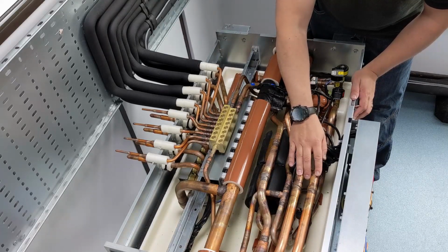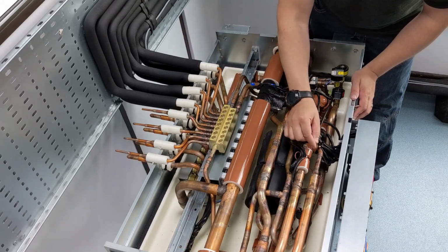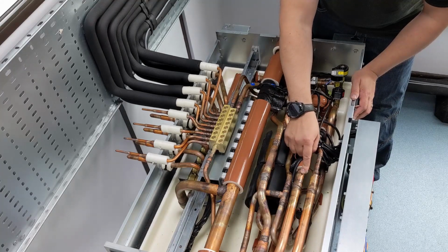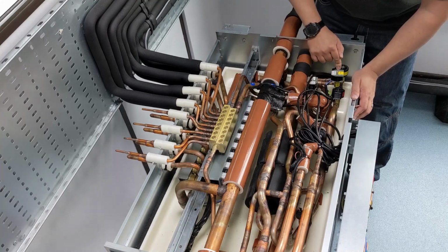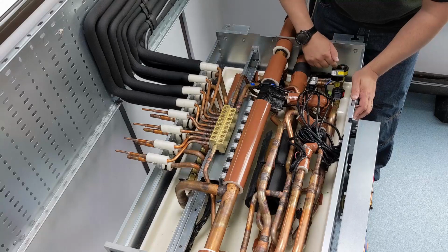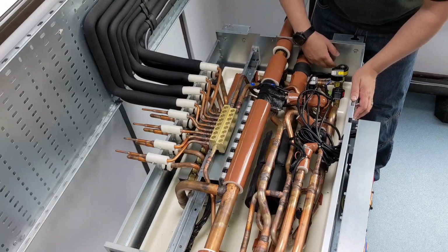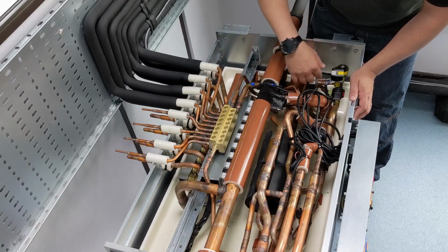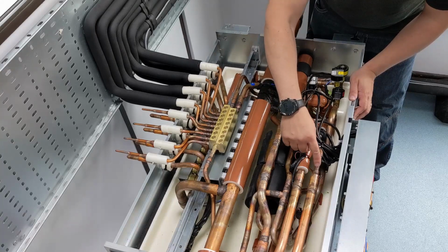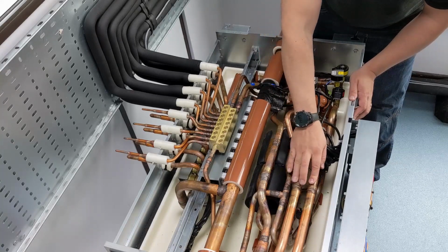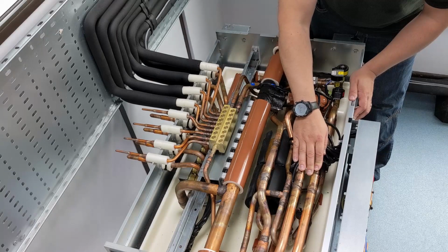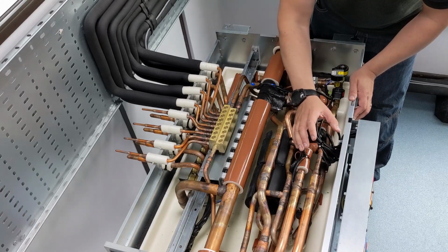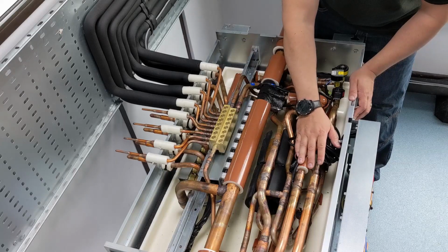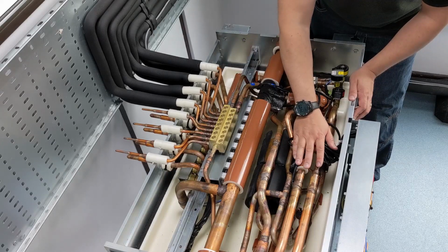The way we're doing that is we're stealing a little bit of refrigerant that should be going through that tube-in-tube heat exchanger, and we're going to feed it through LEV3. So I've now got refrigerant that's dropped in pressure. It's now desperately wanting to boil. I pass that, say, a tube in a tube inside that to subcool it to around about 20 degrees. So the idea being is that when that refrigerant passes off to the indoor units, it's still actually 100% liquid as it goes through the expansion device.